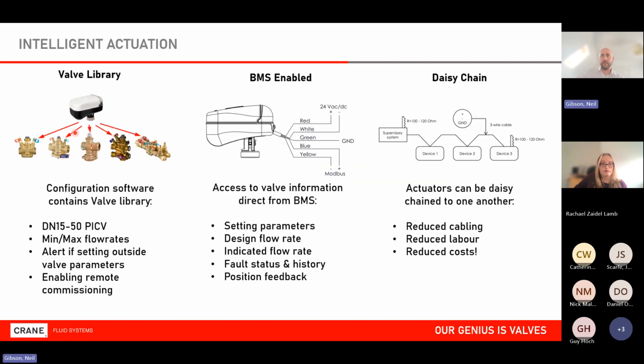So what do I mean by an intelligent valve? Fundamentally, what I've got is something which has got information stored within there, has its own control loops, it has its own intelligence. Typically, you might find that within here, they're BMS enabled, so we can talk via Modbus, in some examples via BACnet, and we can access a huge amount of information. In this example, the valve information is built within here. So I can select via one of the Modbus registers what valve I'm connected to.